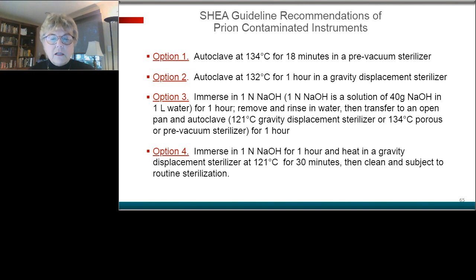Prion contaminated items. The recommendation is that immediate use sterilization, what we used to call flash, should never be used for prion-contaminated items, and I think that's logical, but we need to reiterate it. Always discard single-use devices rather than reprocessing. It's not worth the risk. To minimize the environmental contamination, non-critical surfaces should be covered with a plastic-backed paper. So it's absorbent on the front with the paper. And I realize I'm talking paper here because of its absorbency; something else is fine if they also declare the absorbency. But on the back, to have that fluid resistant plastic coating, so it's not getting on your surfaces.